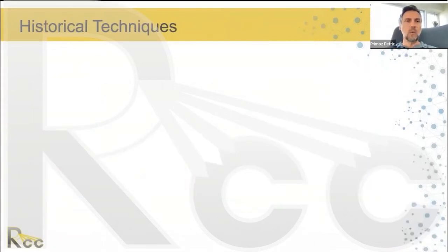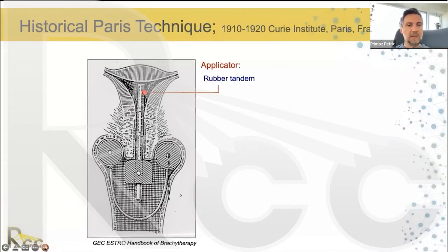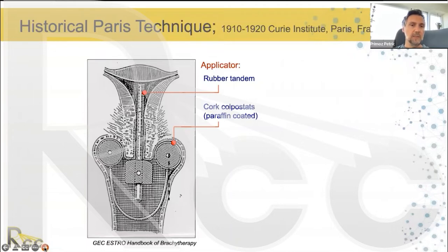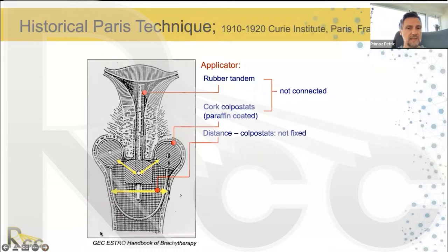When did applicator development actually start? It has been a century since the first brachytherapy for cervical cancer was performed using an applicator at the Institut Curie in Paris, France. That applicator consisted of a rubber tandem inserted inside the uterus and a pair of colpostats inserted into the vaginal fornices on each side. They were made of cork coated with paraffin. The cork colpostats and the rubber tandem were not connected to each other, and the distance between the colpostats was not fixed — it depended on the vaginal dimensions.